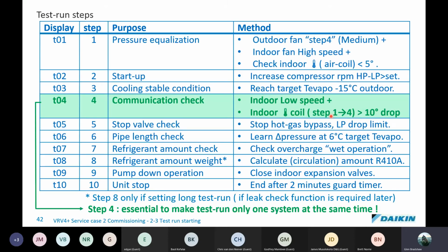The test run logic: the VRV4 systems start out at T01 and run through to T10. T01 is a pressure equalization. The outdoor fan goes to step 4, which is medium speed, and the indoor fan goes to high speed, and they check the indoor air coil temperature, air minus coil temperature less than 5 degrees. Then the startup: increase compressor RPM, with HP minus LP greater than the set value. So basically there must be a difference between the HP and LP pressures as it starts up. T03 is a cooling stable condition, and here it tries to reach the target evaporating temperature of minus 15 degrees, which is set by the main PC board in the unit.